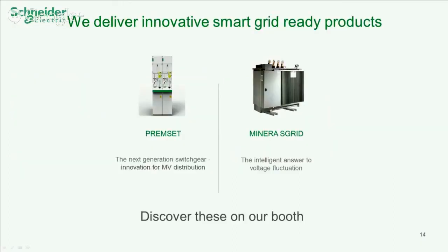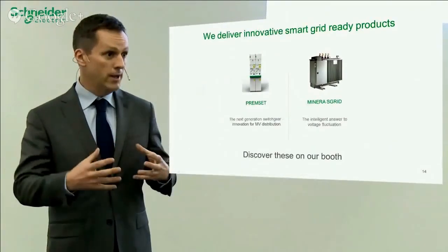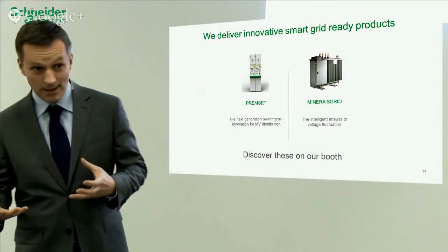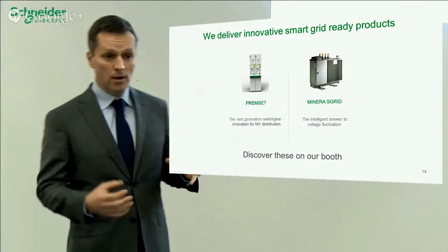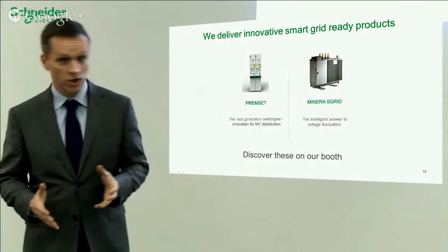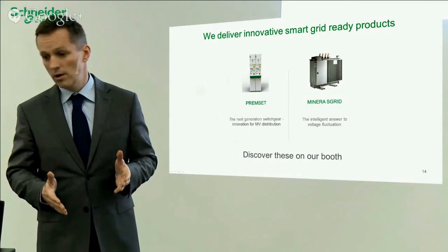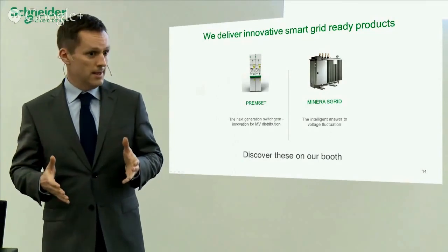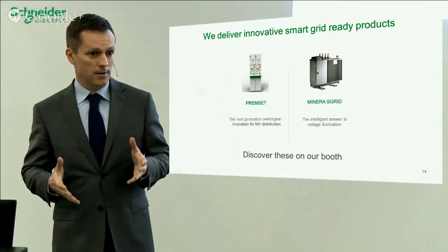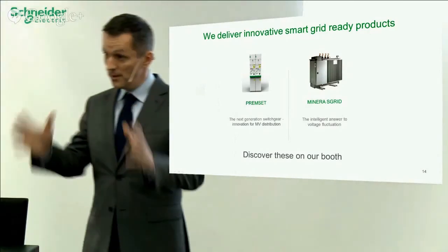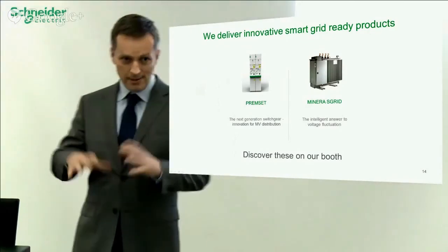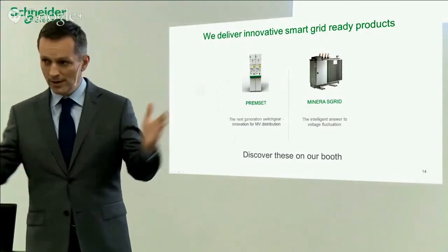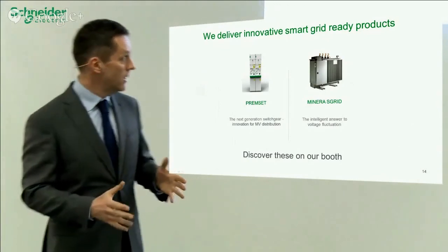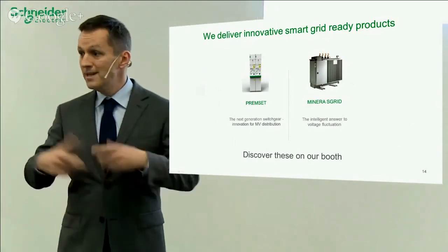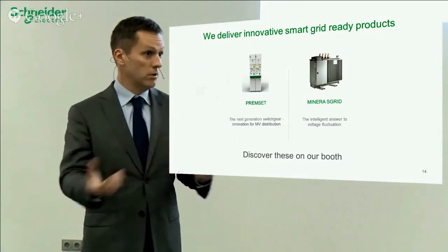All this also works because we are building devices that are already ready to be connected. Here we have two devices. First, our PremSet switchgear, which uses a totally new isolation media, and it's revolutionary because it's a solid insulation instead of gas or vacuum insulation, enabling it to be much more compact. It's also designed to already be connected to the control systems.